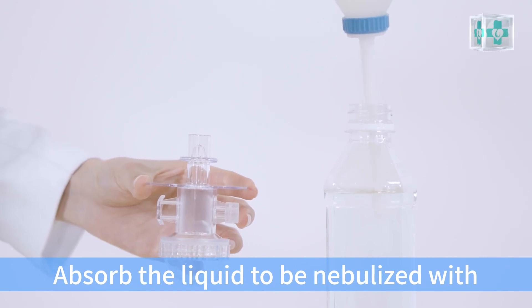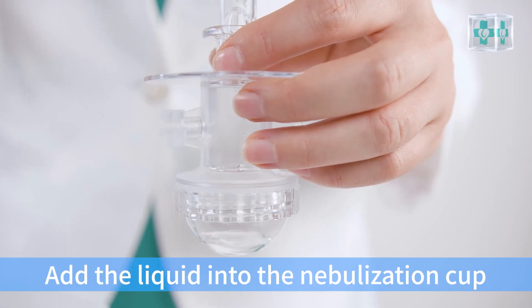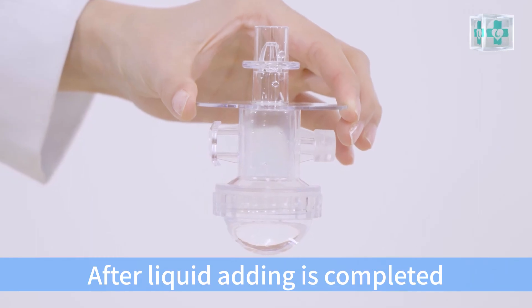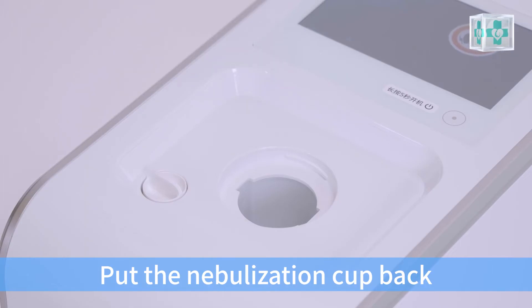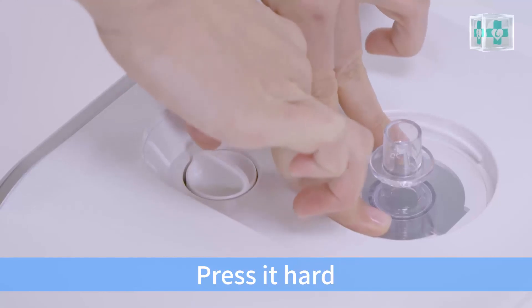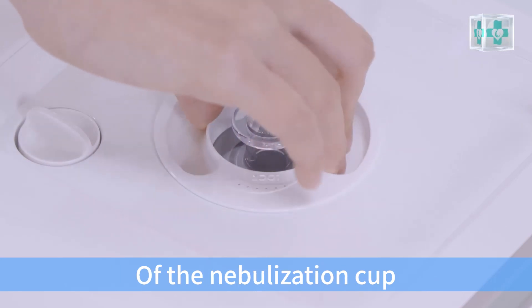Absorb the liquid to be nebulized with a water absorption ball and add the liquid into the nebulization cup. Do not exceed the height at the thread of the semi-circle cap. After liquid adding is completed and confirming that the semi-circle cap is locked, put the nebulization cup back, paying attention to the corresponding direction. Press it firmly. Then screw the top cap of the nebulization cup clockwise.